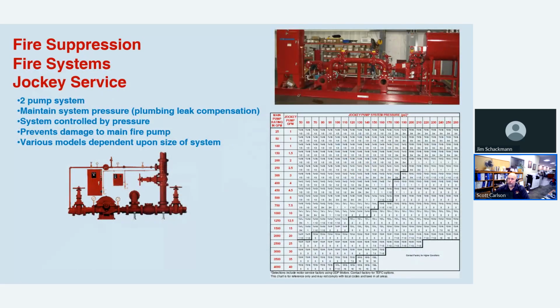Next on our list here is fire suppression systems. In larger buildings, especially in more city type situations and urban situations, you have what's called a maintenance pump or a jockey feed pump. And what that is is that you have your main pump. If there's ever a fire, the sprinklers are activated, the main pump kicks on, and dumps hundreds or thousands of gallons a minute onto the fire through the sprinkler systems to be able to put out the fire.